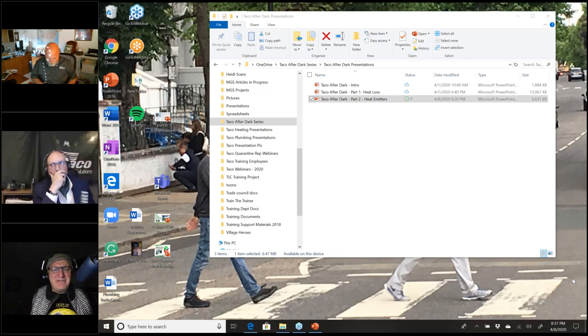A 25,000 BTU zone at zero is a 6,750 BTU load zone at 50 degrees. There's no boiler that turns down that low unless you use a 50,000 BTU boiler. That says Anthony. So yeah, again, worthy discussions to discuss. Yep. Okay. It all depends on the load.